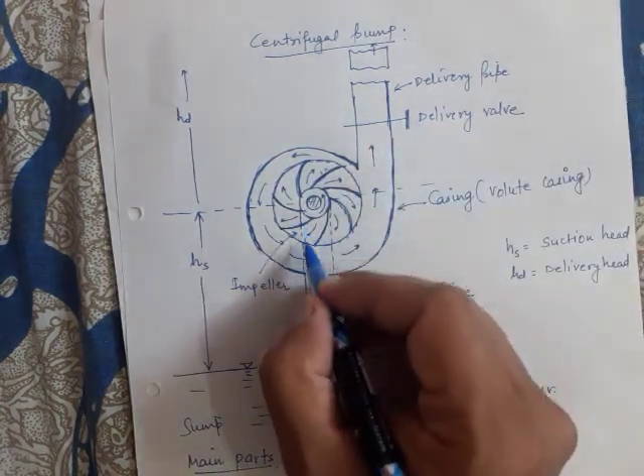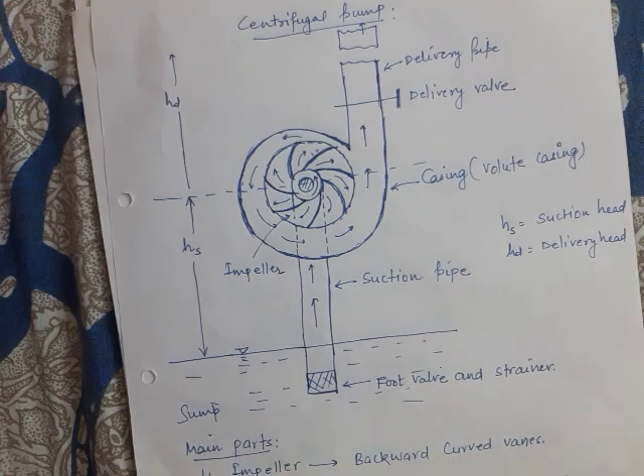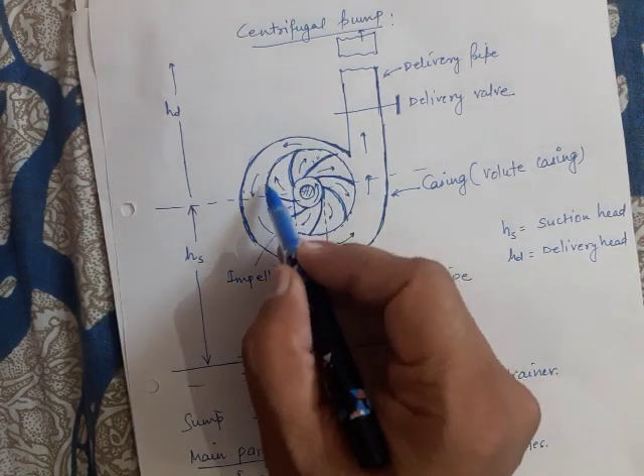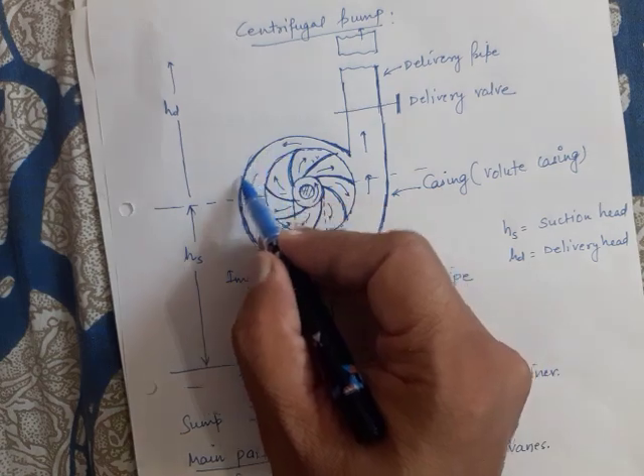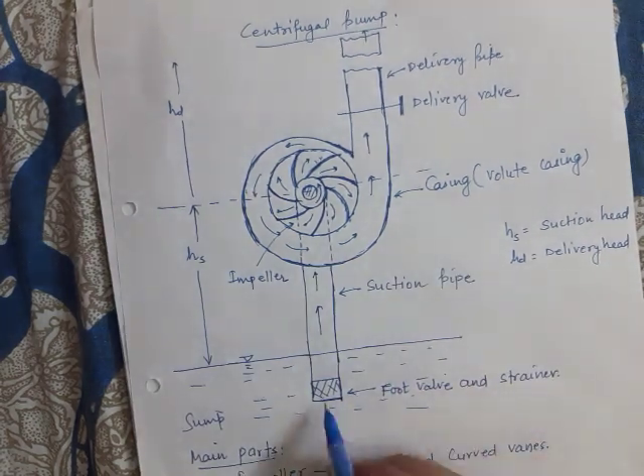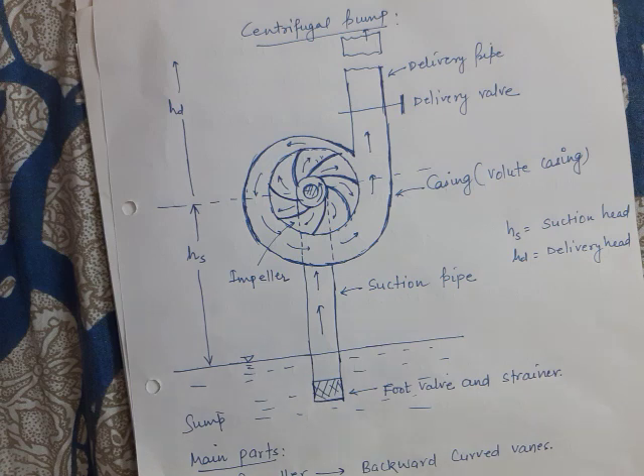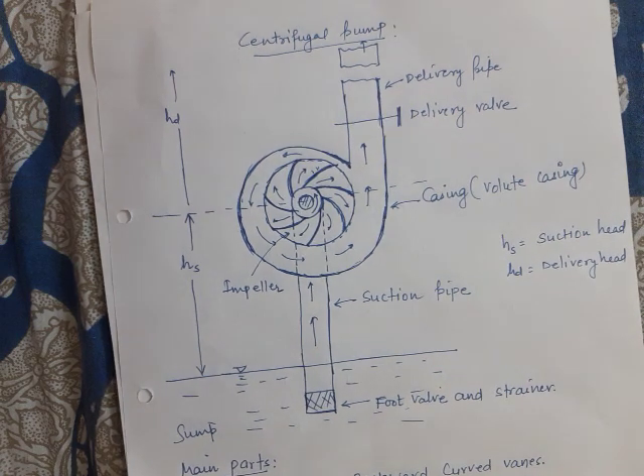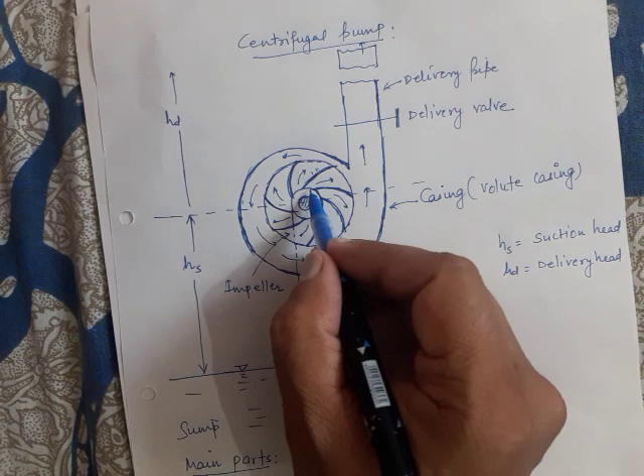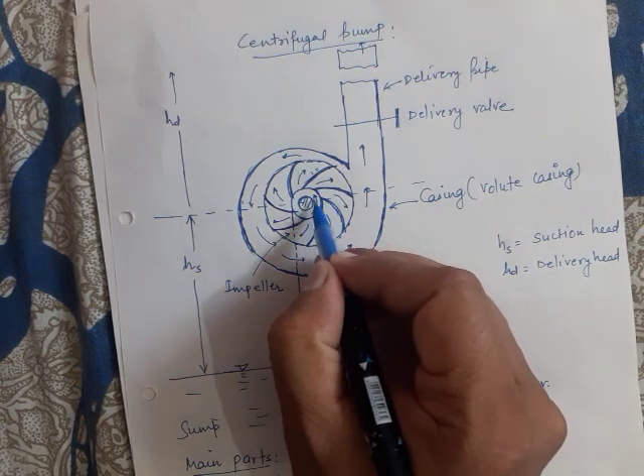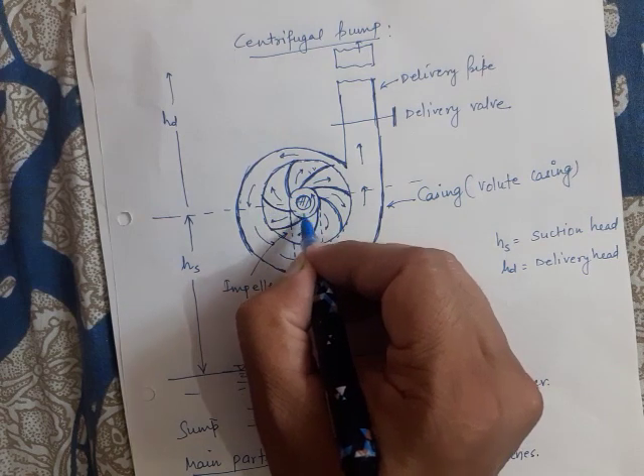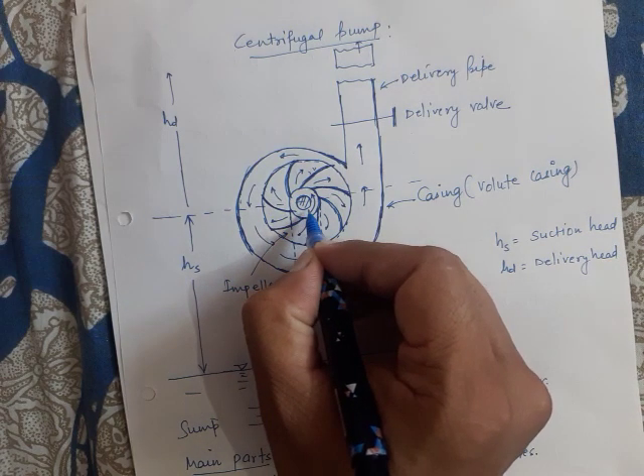The important components of the centrifugal pump are: first, the impeller; second, the casing; third, the delivery pipe fitted with a delivery valve; fourth, the suction pipe; and fifth, the foot valve and strainer. The section at the center of the impeller where water enters is known as the eye of the impeller.